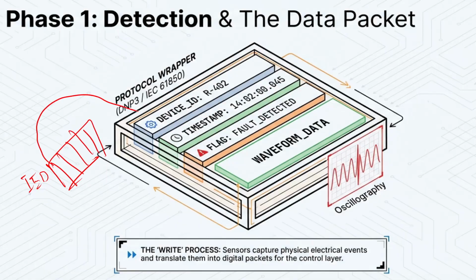This packet will have the device ID - every IED will have one ID, so it could be some ID. Also this will have the timestamp, what specific time it has been triggered. Second is what kind of flag - it has detected the fault. And if we have configured to capture the waveform oscillograph, it will be recorded in this specific payload.